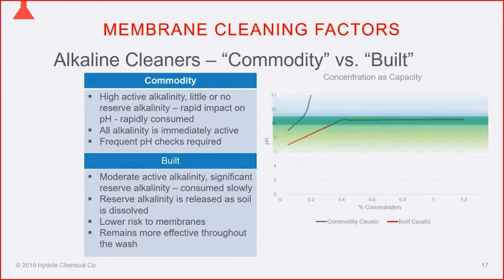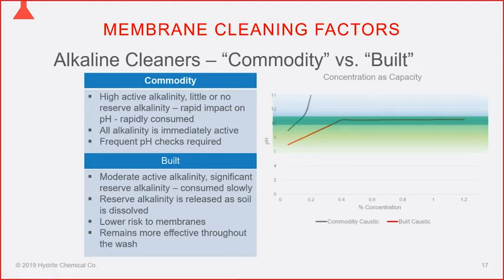Very diligent customers with highly trained staff have successfully used 50% caustic to clean membranes, but as soon as you get a new operator who doesn't know how to maintain pH, or they get busy doing other things, cleaning can be compromised. A built caustic contains the commodity caustic as one ingredient, but a portion of that caustic has been neutralized by an acidic component — for instance, potassium carbonate (potassium hydroxide neutralized with CO₂), or sodium gluconate (caustic with gluconic acid added). These partially neutralized products don't cause pH to spike as rapidly.